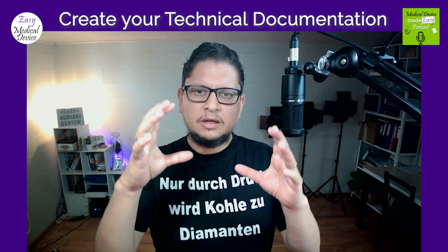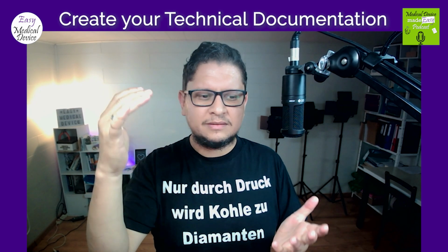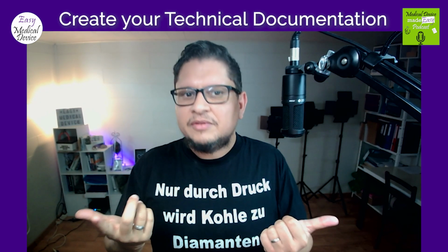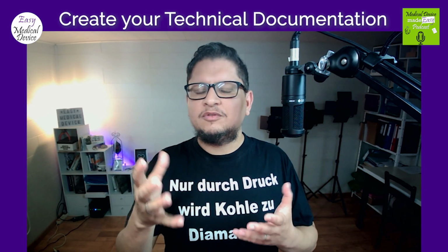So how does it work? You have the sections of the technical file, and you have multiple sections. You have a section, for example, called device description and specification. Here you mention elements such as: what is the name of this device, who is the manufacturer of this device, what is the Basic UDI-DI, you can put the UDI-DI, you can also put the classification of the product and the conformity assessment. This is basic information that is provided.